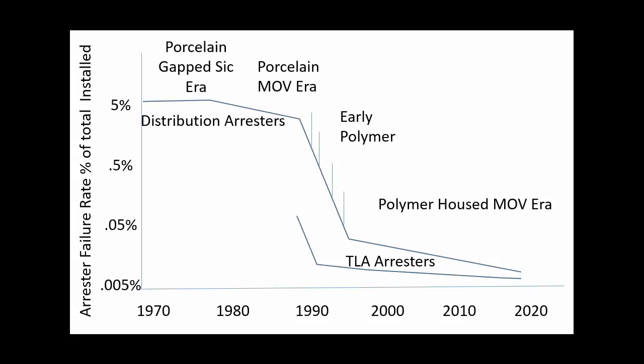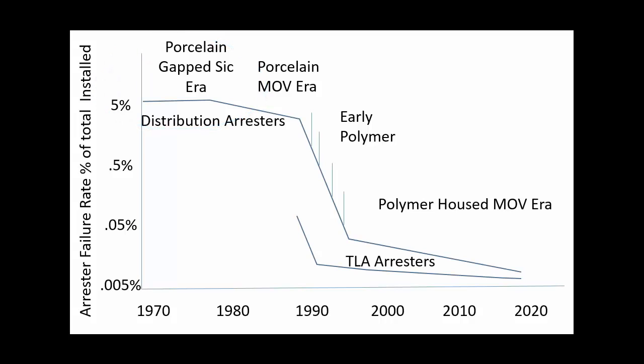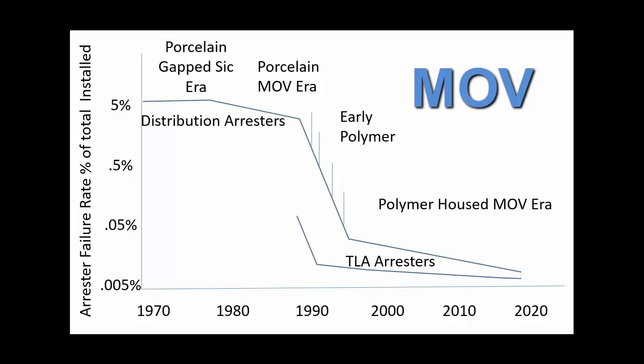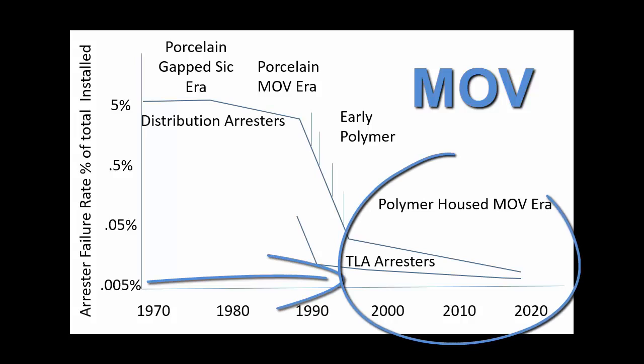One of the biggest concerns of those using transmission line arrestors for the first time is the long-term reliability and maintenance of the arrestor. There was a time when gap silicon carbide arrestors had questionable reliability. However, in this mature MOV arrestor era, reputable suppliers have consistently achieved arrestor failure rates that are close to that of the insulator in the PPM range. Look at the reliability record of your existing equipment MOV type arrestors — you will be surprised at how low a failure rate you are experiencing if you remove the old Porcelain gap arrestors from that population.